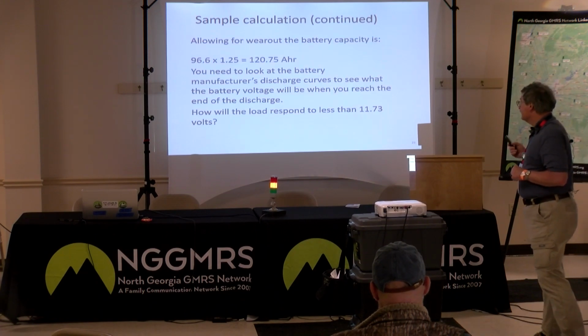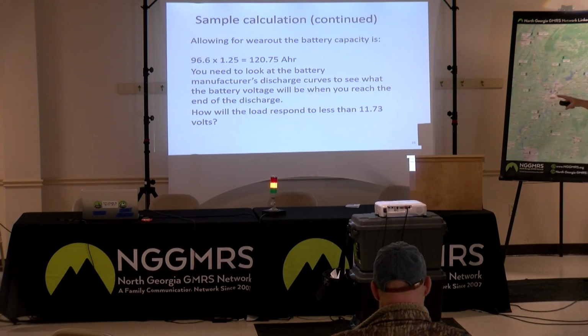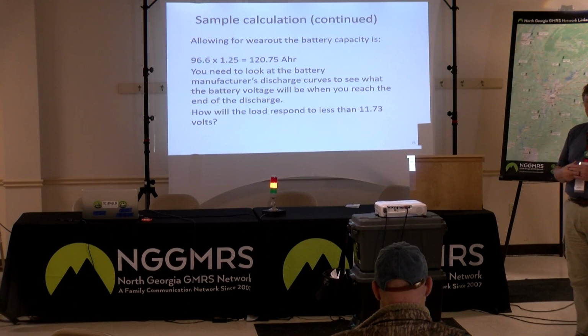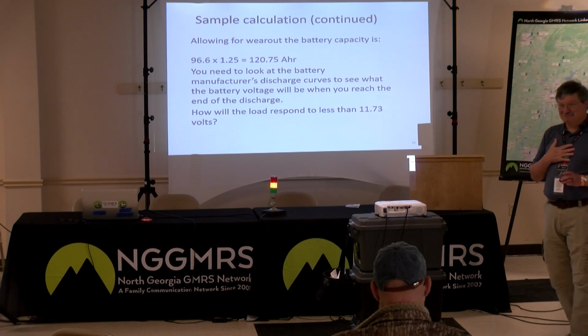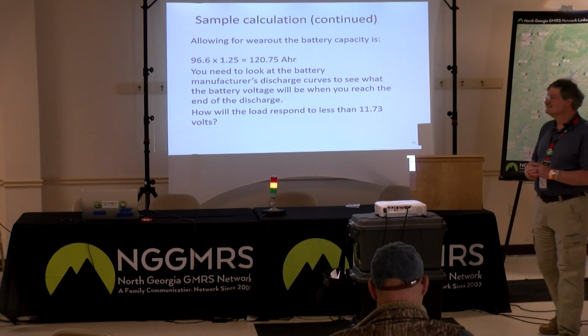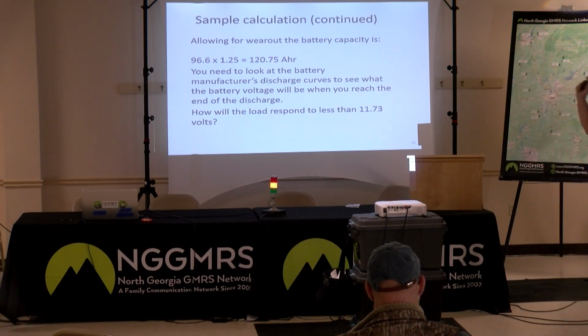So here I've used the 1.25 because of the 80% for the battery wear out, and that puts me to 120.75 ampere hours. Given the accuracy of some of the estimates, a 120 ampere hour battery would probably be fine. 125 would be okay. I'm going to try not to be out in Minnesota winter weather, in a blizzard. But as I say, you need to look at the manufacturer's discharge curve to see what it'll do. I already mentioned, how's that load going to respond when you get below that 11.73 volts?